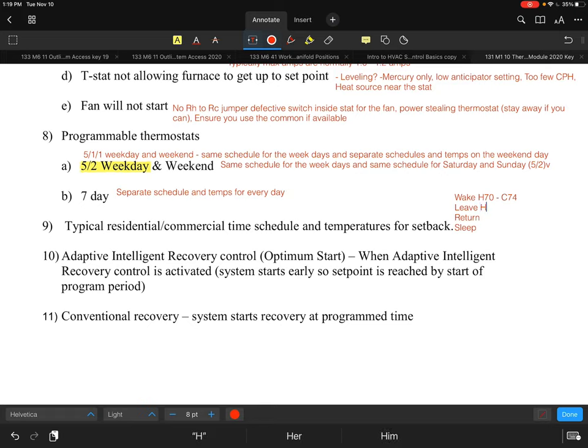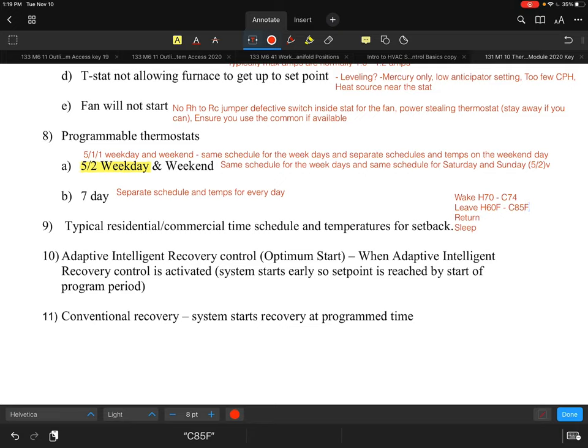When you leave and nobody is occupying the building, you set what's called a setback temperature. For heating, you might let it drop to 60 degrees Fahrenheit. For cooling, you might allow the house to warm up to 85 degrees while you're away. These are setback temps — the key consideration is whether your system can recover by the time you return.